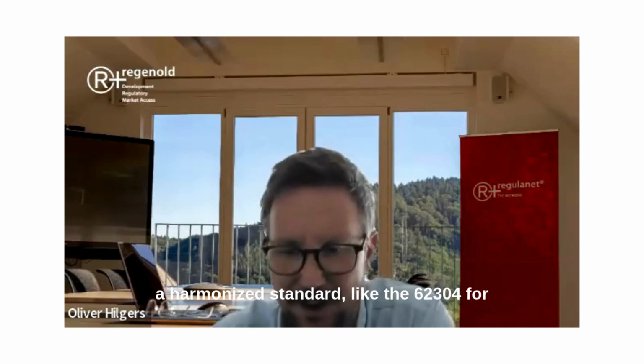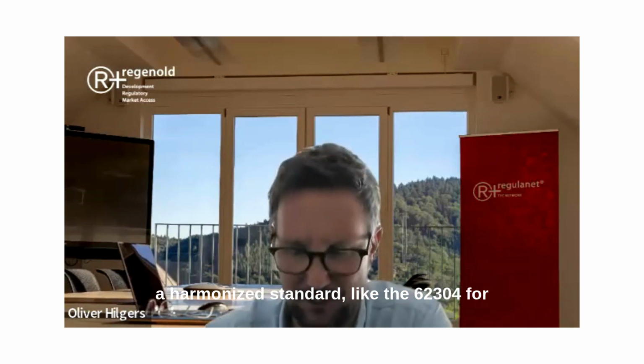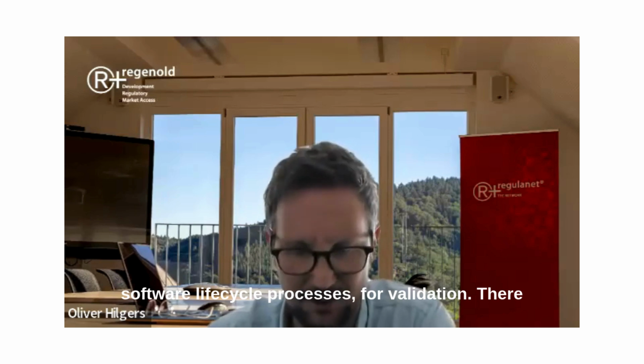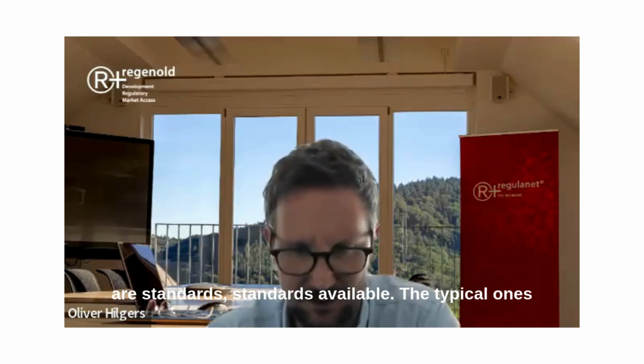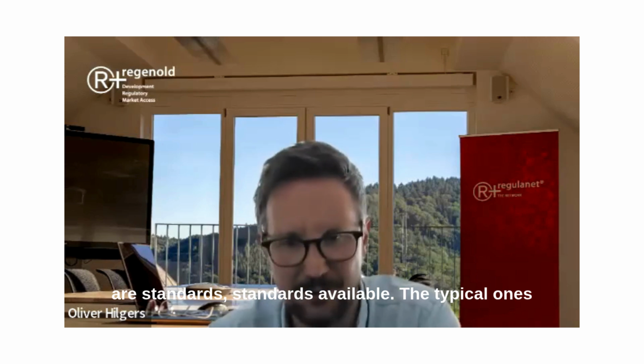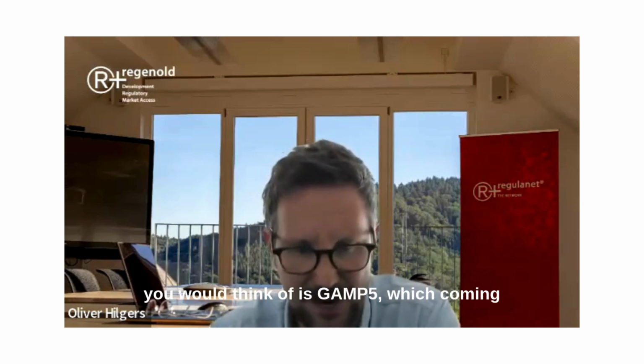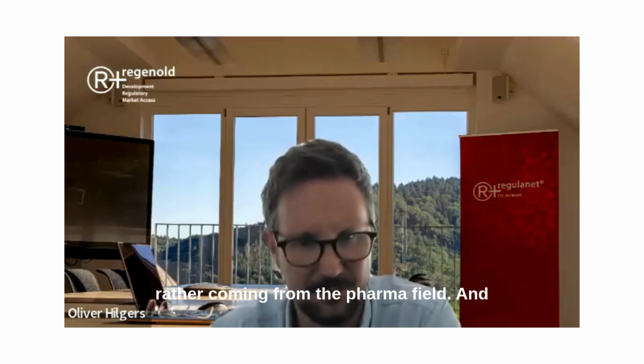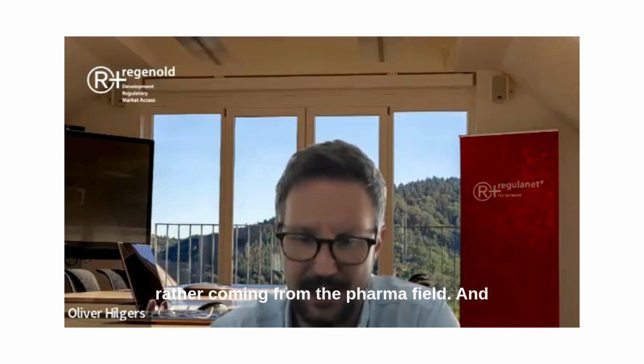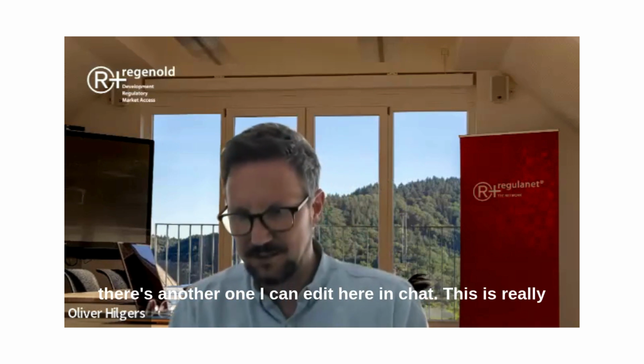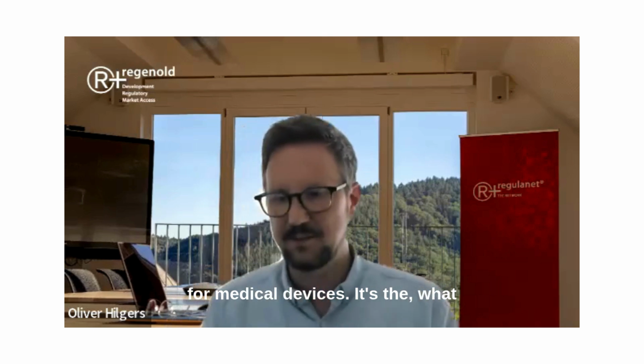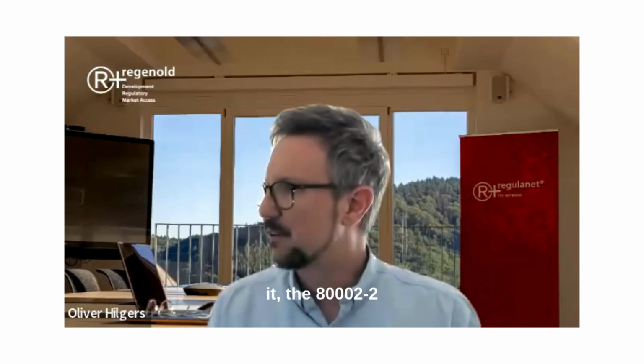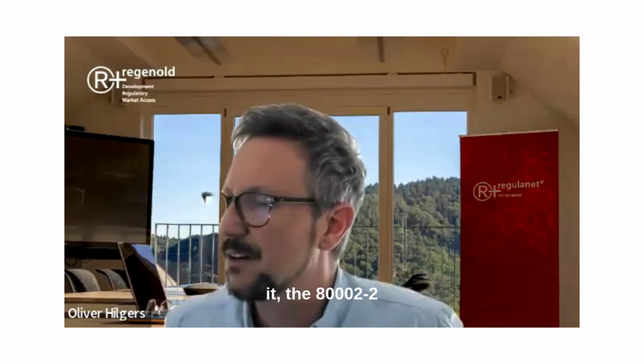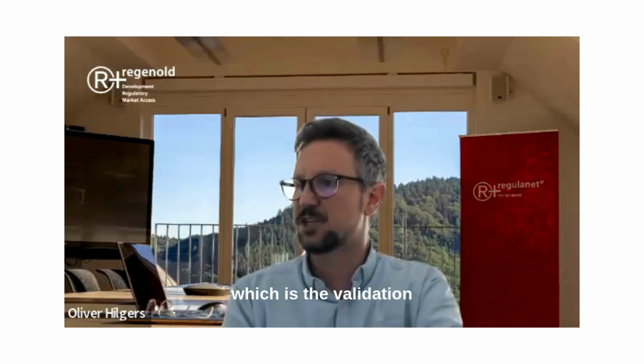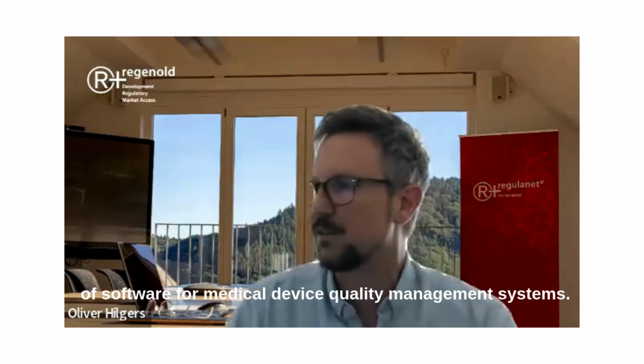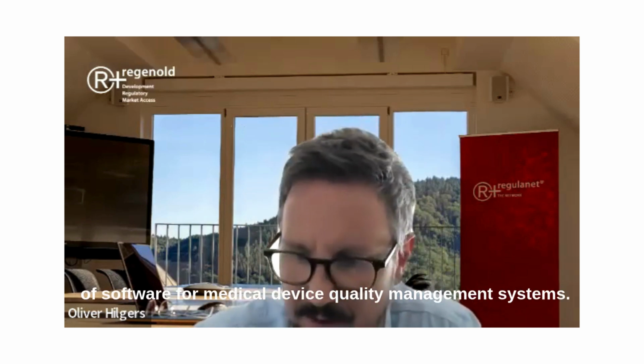Yeah, maybe just to add on Thomas, Matteo, I think it's very important to understand there's no harmonized standard like the 62304 for the software lifecycle process for this validation. There are standards available. The typical one you would think of is GAMP 5, which is coming from the pharma field. And there's another one I can add here in the chat. This is really for medical devices. It's the 80002-2, which is the validation of software for medical device quality management systems.